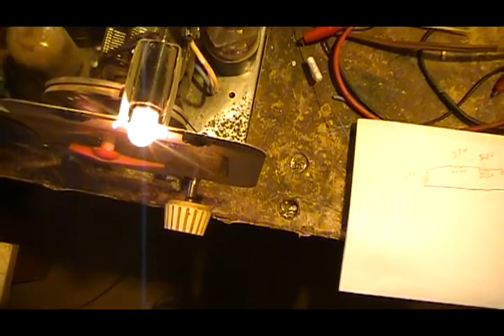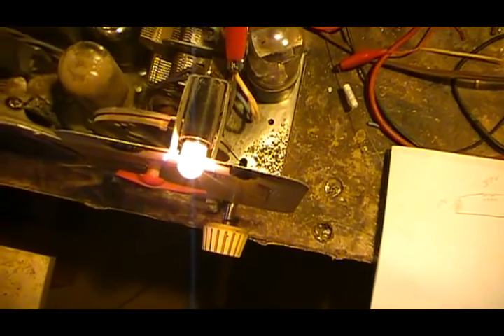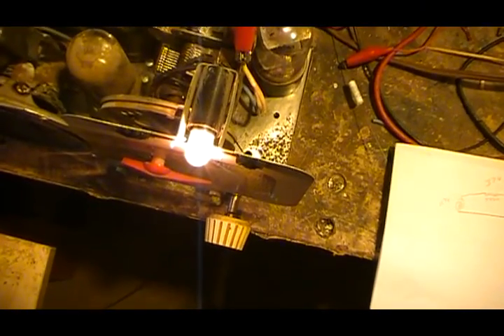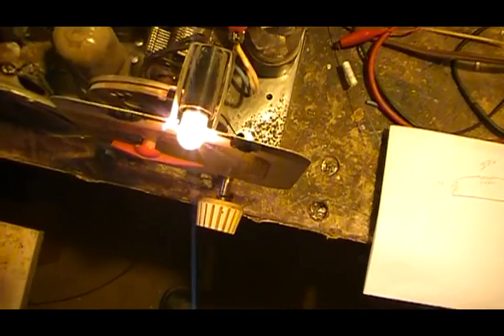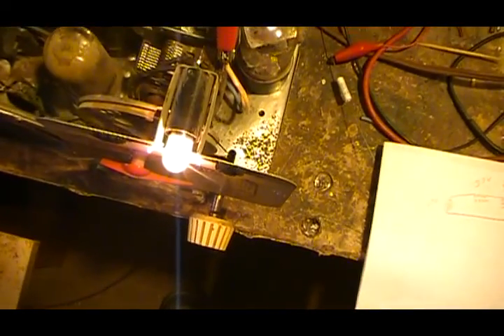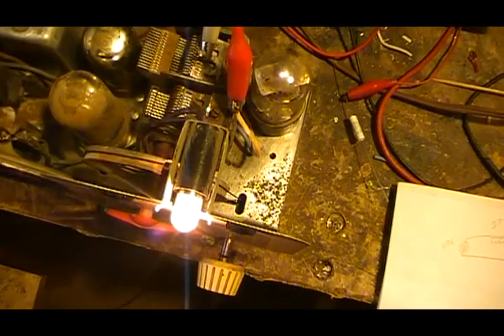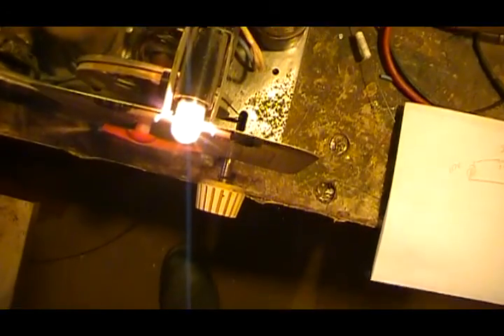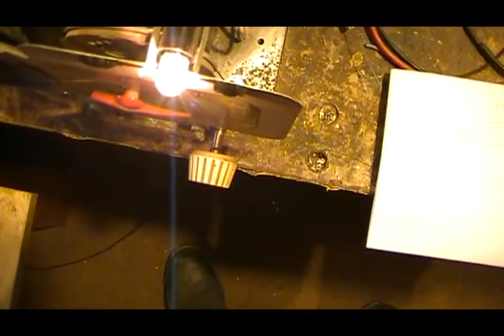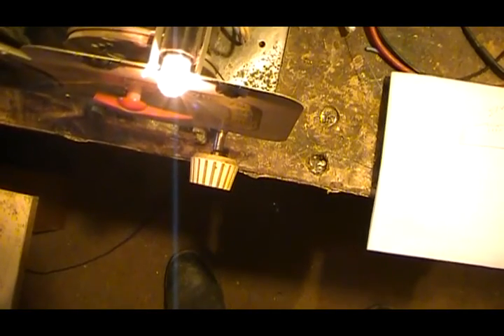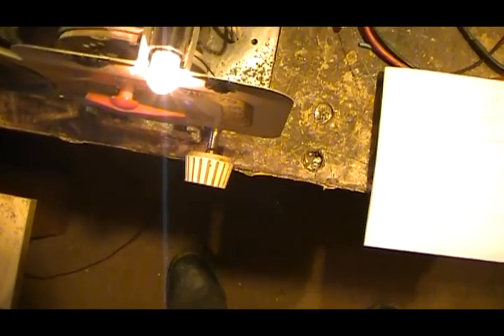The dial light may dim down real dim, and if you're watching an amp meter, you'll see it really draw, then start coming back down. If you're using a dim bulb tester, it'll flash real bright and then dim down. The main reason is the cold resistance draws a lot of current right off the bat, and as the tubes heat up, the resistance goes up.